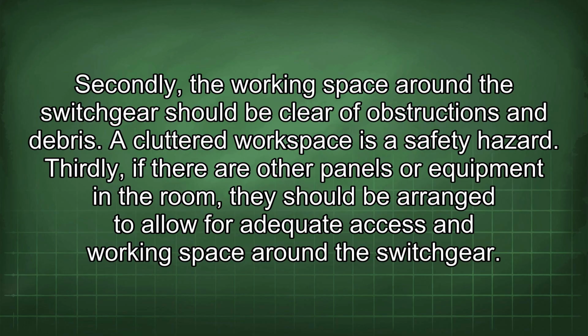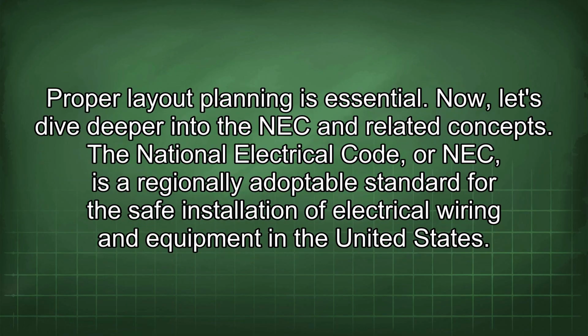Secondly, the working space around the switchgear should be clear of obstructions and debris. A cluttered workspace is a safety hazard. Thirdly, if there are other panels or equipment in the room, they should be arranged to allow for adequate access and working space around the switchgear. Proper layout planning is essential.